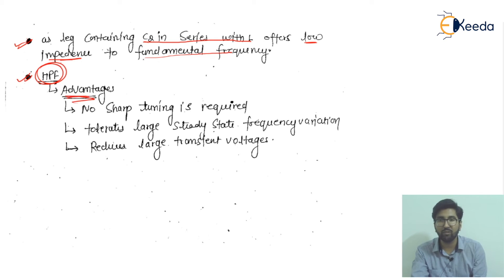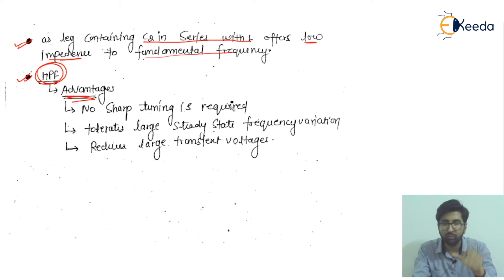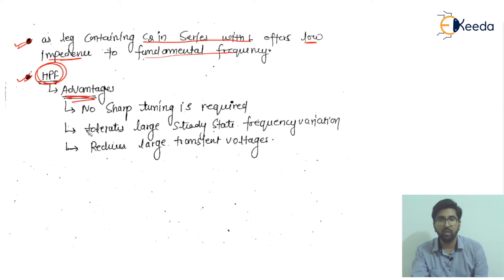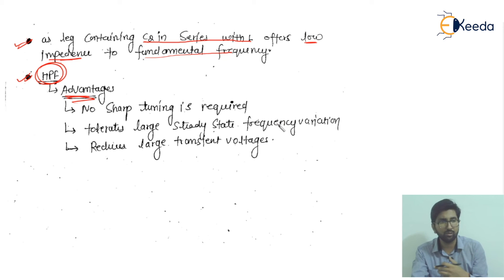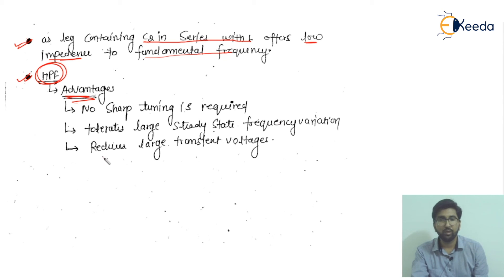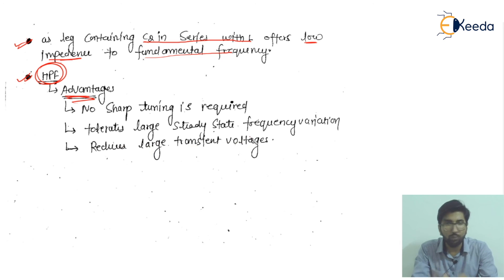The advantages of the high-pass filter are: first, no sharp tuning is required, as it operates across a band beyond the cutoff frequency. Second, it can tolerate large steady-state frequency variations in the system. Third, it provides protection by reducing large transient voltages. So the high-pass filter not only filters harmonics but also offers system protection.